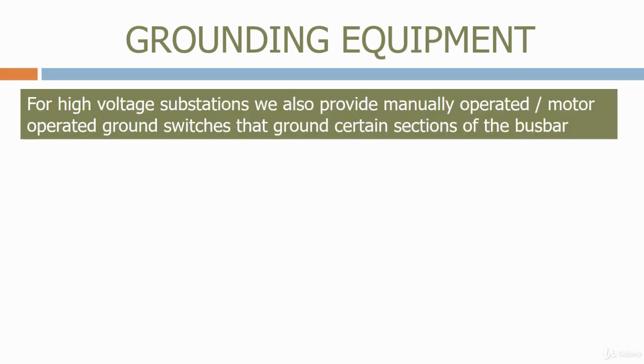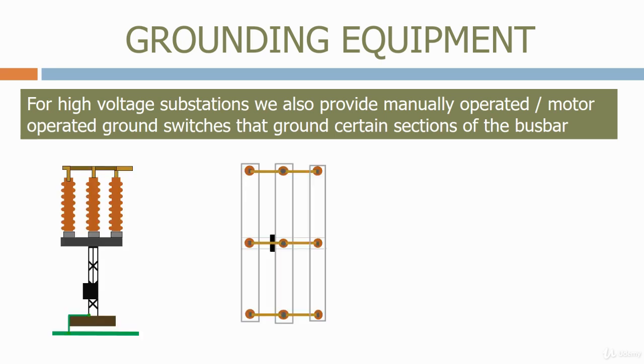For high voltage substations, we also provide manually operated or motor operated ground switches that ground certain sections of the busbar. These are normally positioned on the substation isolators. They could be positioned on either side of the isolator. Here's an example where the ground switch has been positioned on the right-hand side of the isolator. The ground switch is given its own direct grounding connection to the substation ground grid. This has to be rated to carry the full short circuit current in case the ground switch comes into contact with a live conductor.